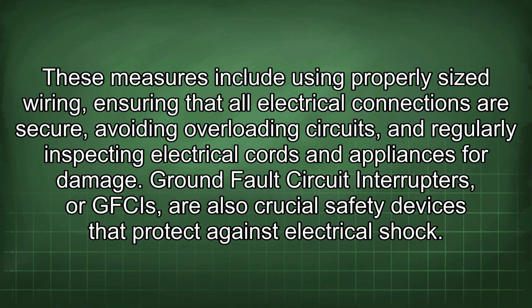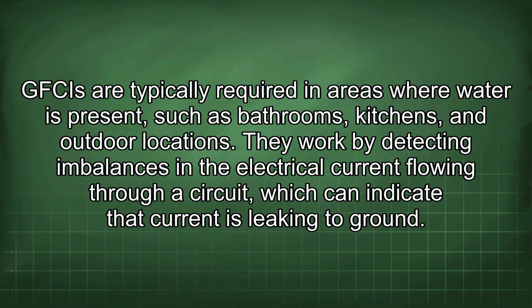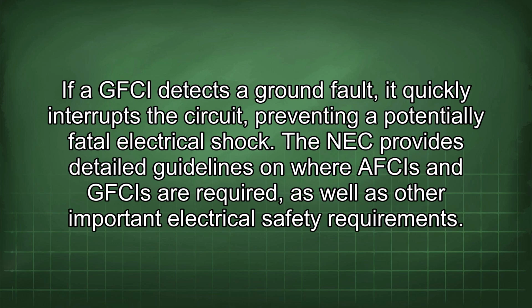Ground fault circuit interrupters, or GFCIs, are also crucial safety devices that protect against electrical shock. GFCIs are typically required in areas where water is present, such as bathrooms, kitchens, and outdoor locations. They work by detecting imbalances in the electrical current flowing through a circuit, which can indicate that current is leaking to ground. If a GFCI detects a ground fault, it quickly interrupts the circuit, preventing a potentially fatal electrical shock.